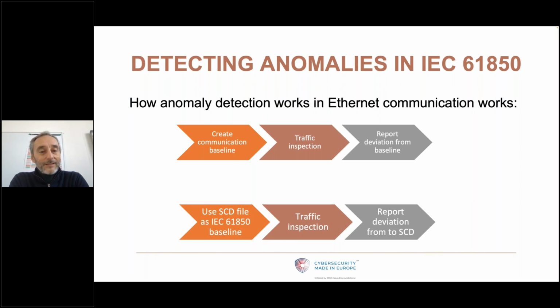Edwin mentioned this at the beginning of the webinar. We can use the SCD file, because in 61850 this file describes the full communications between IEDs and endpoints. So if your MMS server, MMS client, or GOOSE publisher isn't defined in the SCD, that's an anomaly, and you can report it.